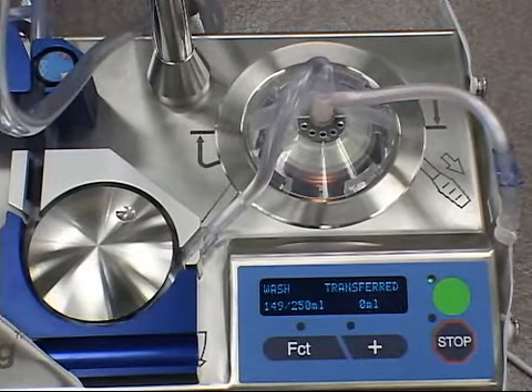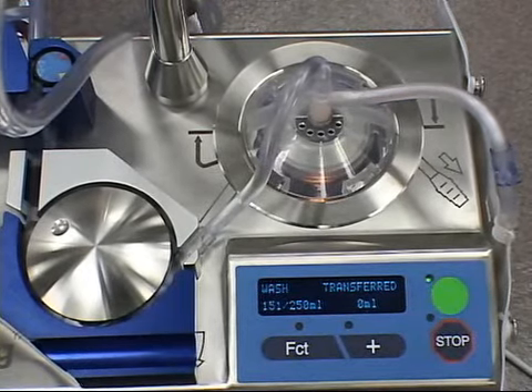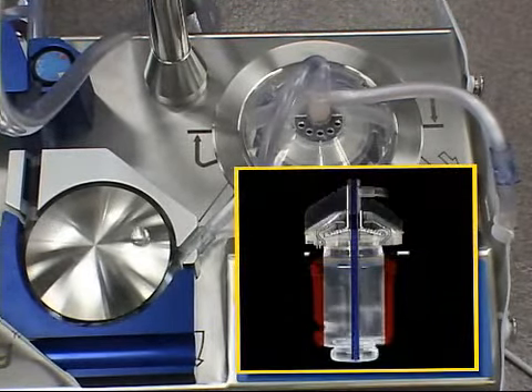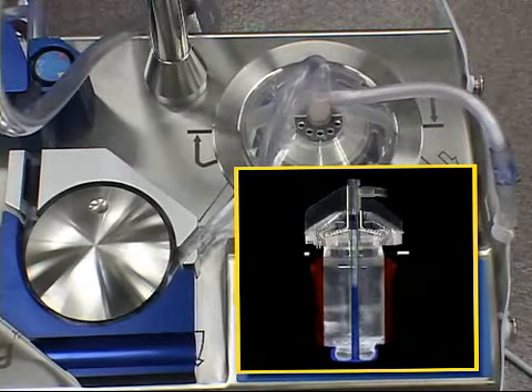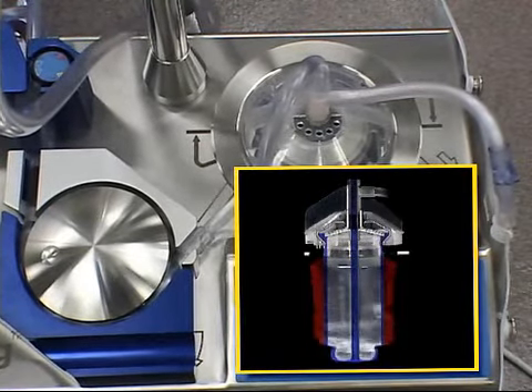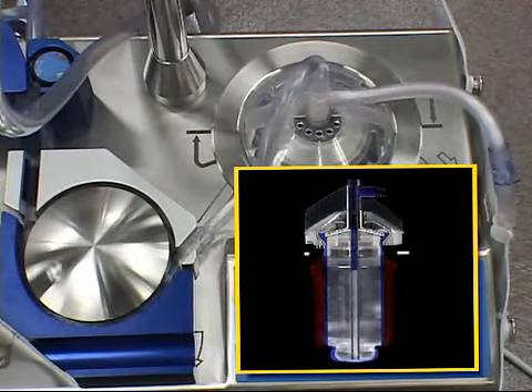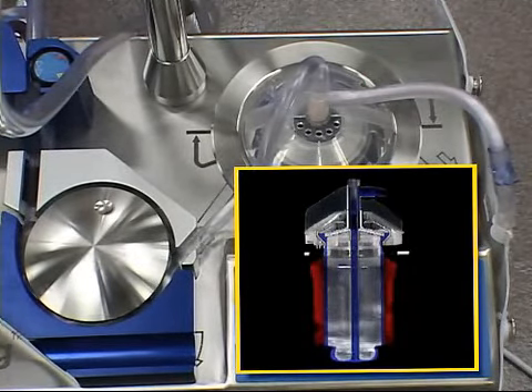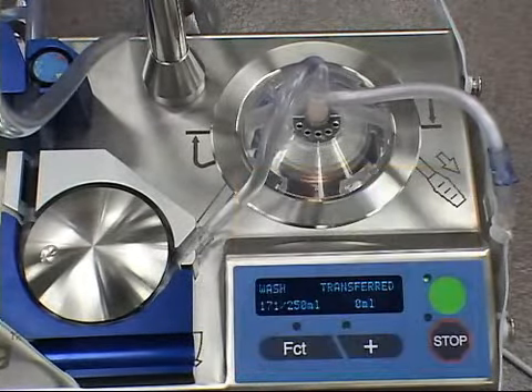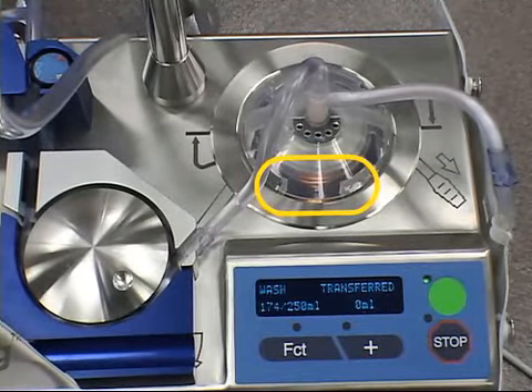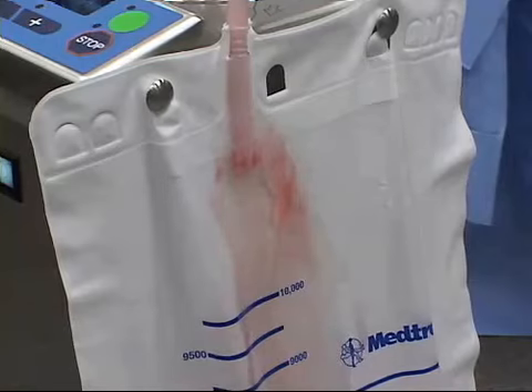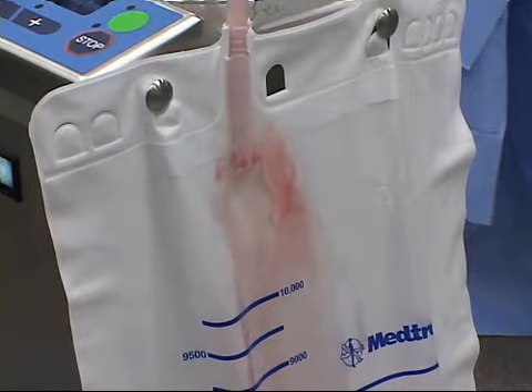The AutoLog then employs a variable pulsed wash cycle. The level sensor continuously monitors the red cell pack, and the software controls the fluid pump to inject variable pulsations of saline into the bowl as determined by the microprocessor. The unique AutoLog bowl indentations and wash pulsations generate alternative fluid channels so that the saline wash solution travels thoroughly through the red blood cell pack. Only 250 milliliters of saline are required for a safe and effective washout of all extraneous materials.